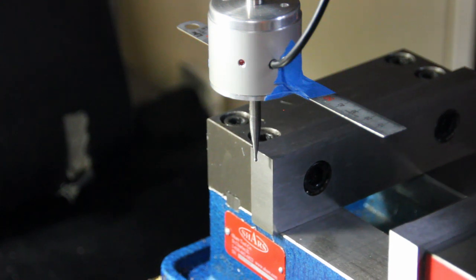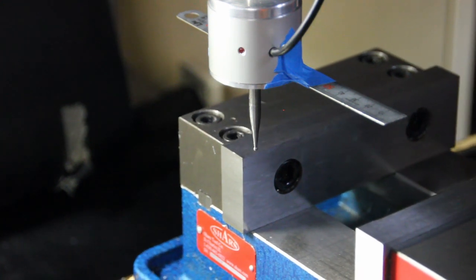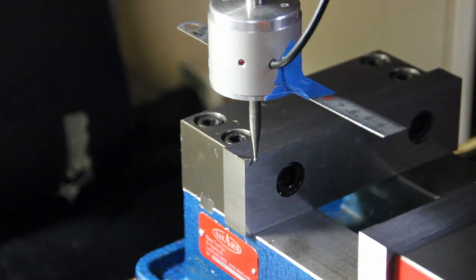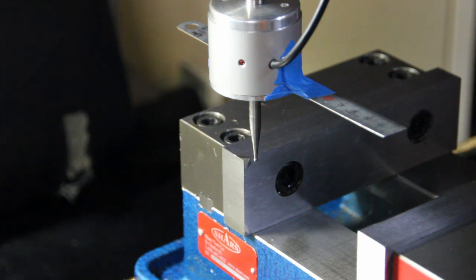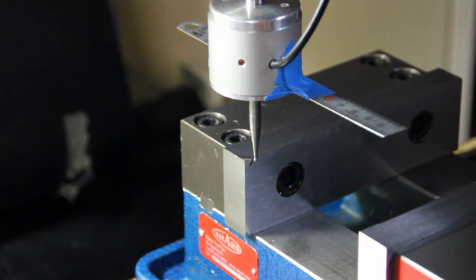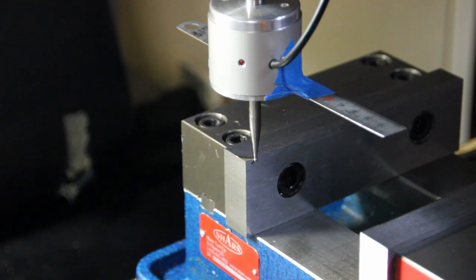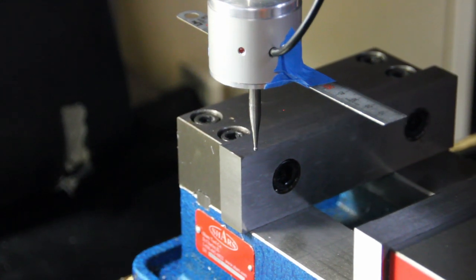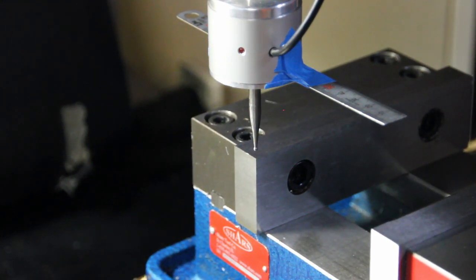And I think I could speed up my final probe. I played with it a little bit before. I had it, I think, at 3 inches a minute, and I brought it down to 1 inch a minute. But I think I could go back up to 3 inches a minute and it not have any adverse effects on the accuracy. So that time we were off in X by 0 10,000ths, and we were off in Y by 5 10,000ths.